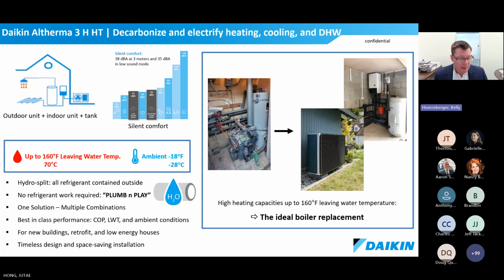And we can do that as low as minus 28 C, or minus 18 Fahrenheit. So that's fantastic, it's a really strong heat pump system. It's designed for ultra cold climate environments. These systems are operating in Europe, in Norway and Finland, and areas where heat pumps are adopted a lot more rapidly. They're utilizing these particular systems. So imagine those environments analogous to North America. That would be your Wisconsins, your Michigans, up into Manitoba, into Canada, into the northern territories. That's really strong performance in cold conditions.